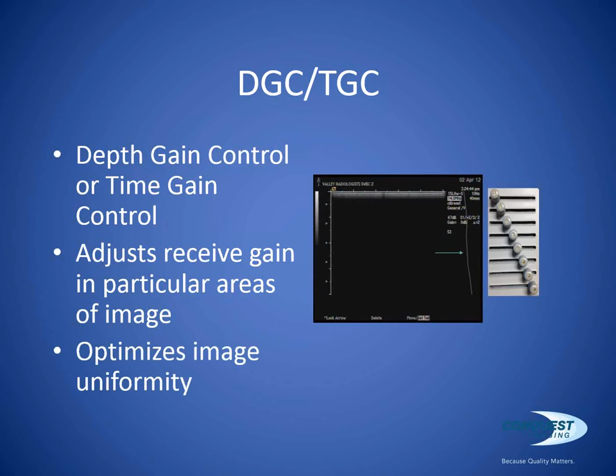Frequency. This is something that when I started in ultrasound back in '86, back when ultrasound machines were powered by coal, all transducers had one operating frequency. A 3.5 megahertz transducer was a 3.5 megahertz transducer. It transmitted at that frequency, it received at that frequency. Ultrasound has come a long way since then. Today's ultrasound systems have a multitude of frequencies, and this allows you to tune the frequency to the body part that you're looking at and the body type. You can see the little green arrow in this image here pointing at 14 megahertz. So you can see above that my probe type is a 15L8W, and below that it shows that I'm scanning at 14 megahertz.